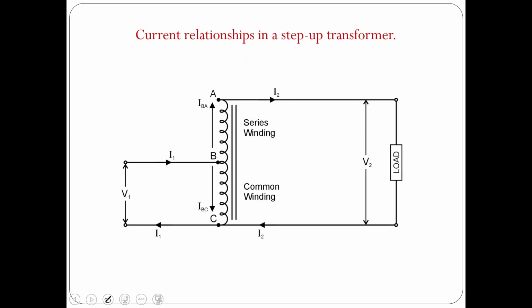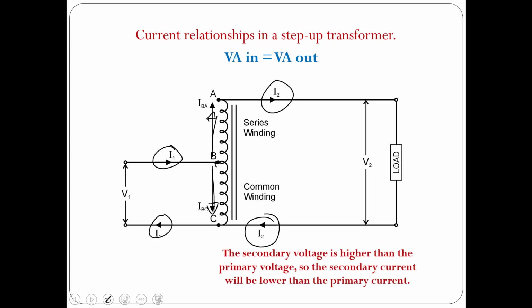Same thing when we're looking at the step up autotransformer. All right, if we know the VA output, that's going to be equal to the VA input. So we can use that VA load that this transformer is under on both the primary and secondary, calculate the current coming in from the source and returning, and then calculate the current going out to the load and returning. From there, we'll balance it out, and we can see how much current is on the series and how much is going to be on the common winding. So let's give you an example with this and start working with this.